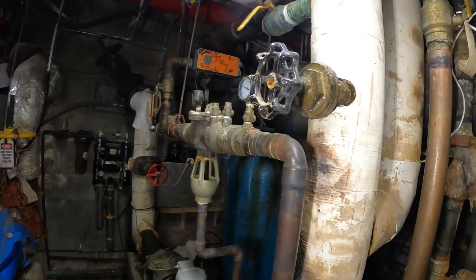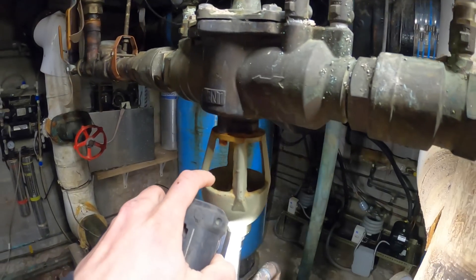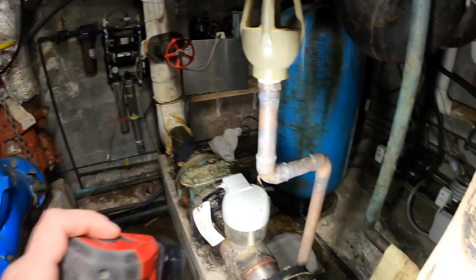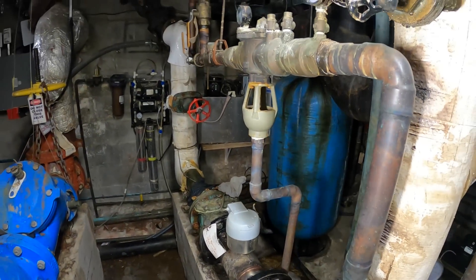So if we look here, this right here is a backflow preventer. This is the air gap and this is the drain for it. The other day the engineer sent me a video where water was actually backflowing up and pouring water everywhere.